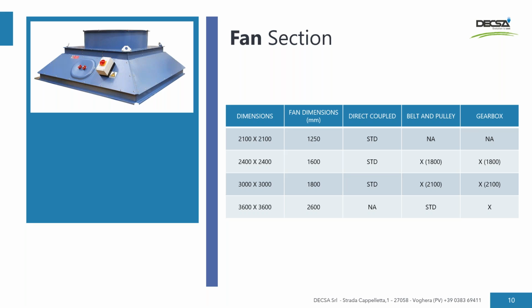What is interesting about the fan section is also the setup of it. Based on the dimension of each cell, we have different types of transmissions available. Let's start with the smaller cell, the 2100 by 2100 millimeter cell. In this case, we can only have the motor directly coupled to a 1250 millimeter fan. On the 2400 by 2400 and the 3000 by 3000 cells, as a standard, we have the direct coupled motor as well.